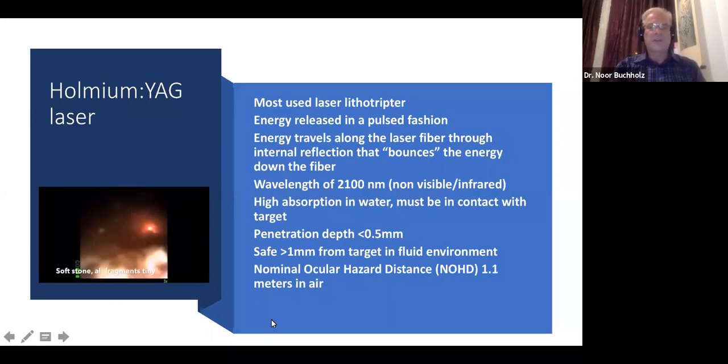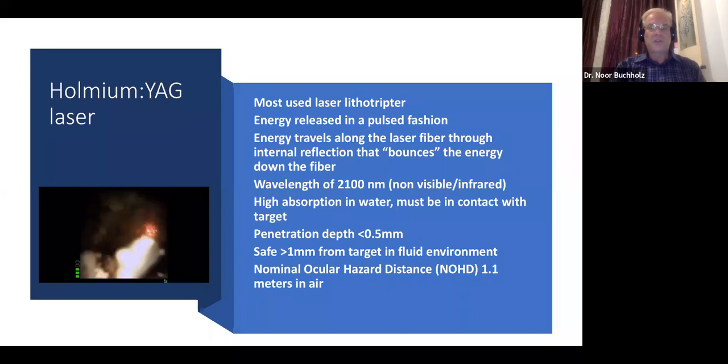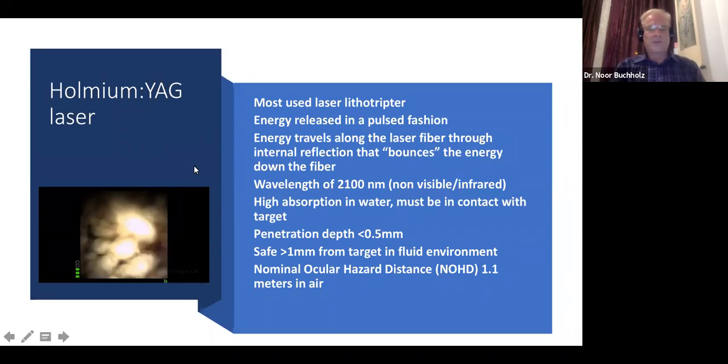Wavelength, we said already, is 2,100 nanometers. There's a very high absorption in water, which means it must be in contact or close contact with the target. The penetration depth in tissue is only 0.5 millimeter. That means if you're more than 1 millimeter from the target in a fluid environment, then nothing should happen.